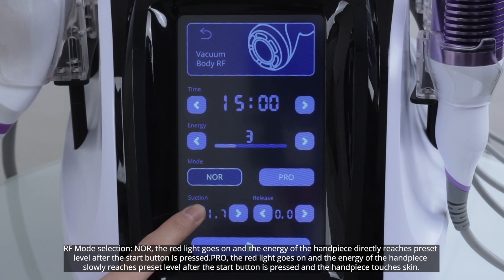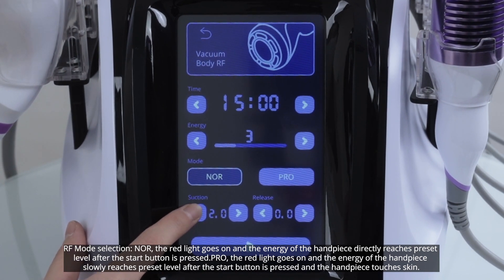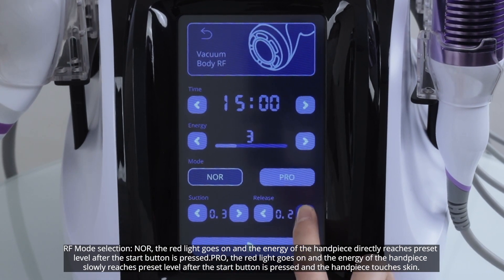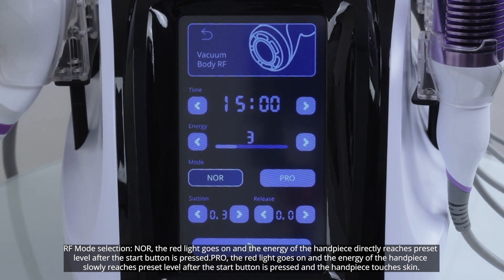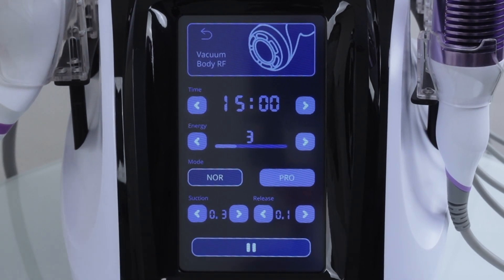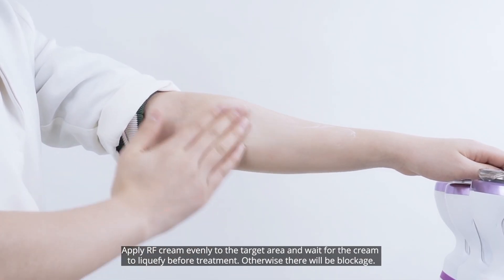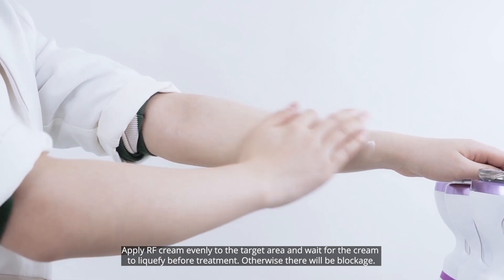RF mode selection: NOR — the red light goes on and the energy of the handpiece directly reaches the preset level after the start button is pressed. Pro — the red light goes on and the energy of the handpiece slowly reaches the preset level after the start button is pressed and the handpiece touches the skin. Apply RF cream evenly to the target area and wait for the cream to liquefy before treatment; otherwise there will be blockage.